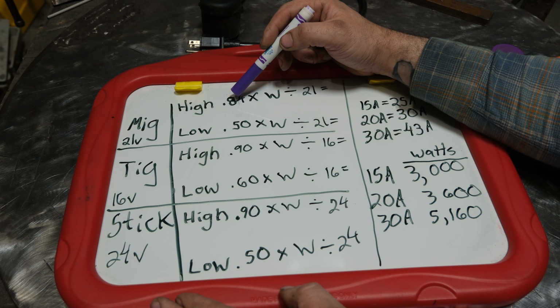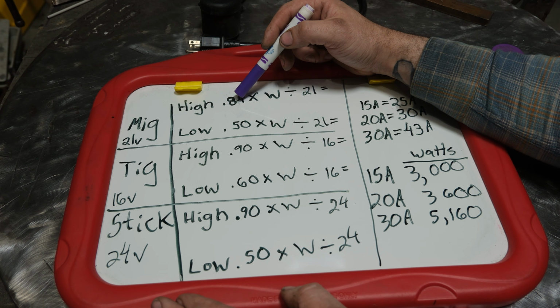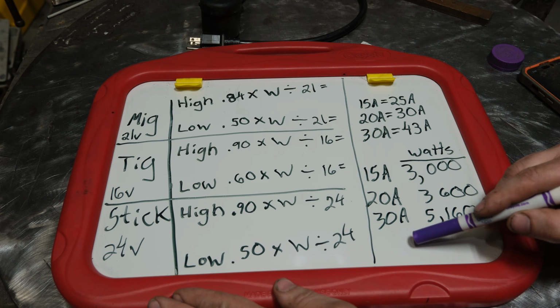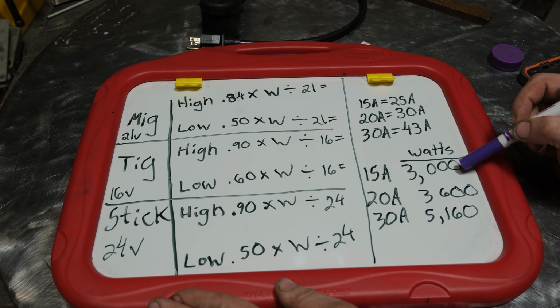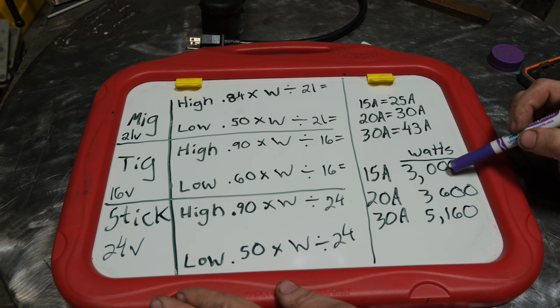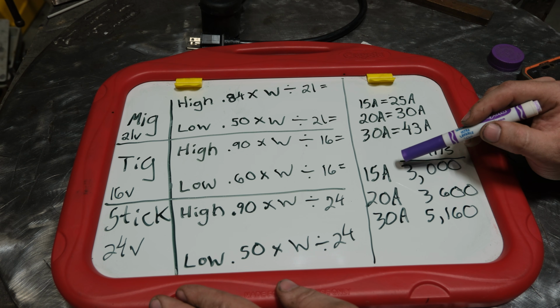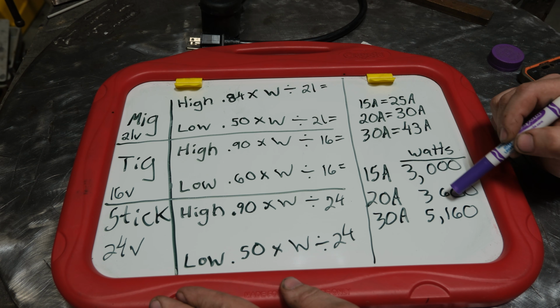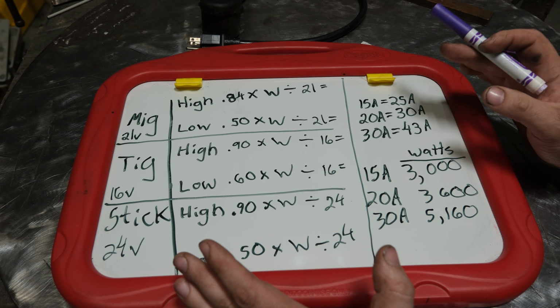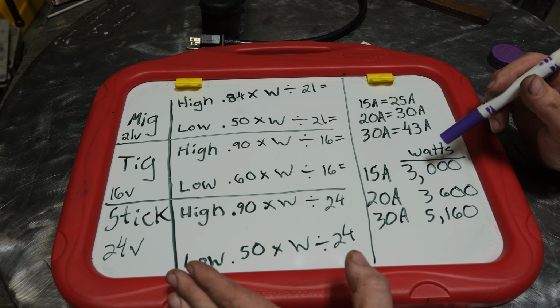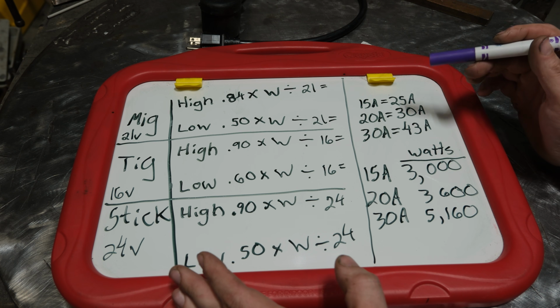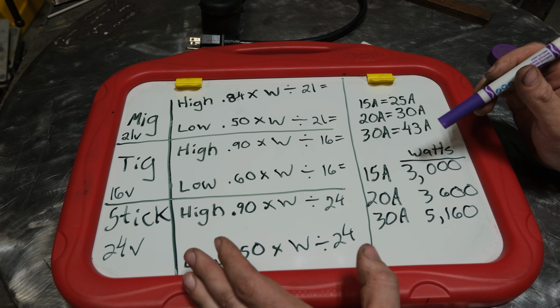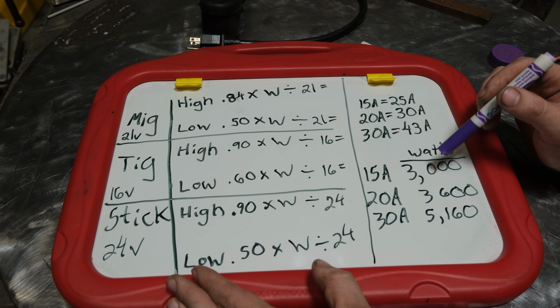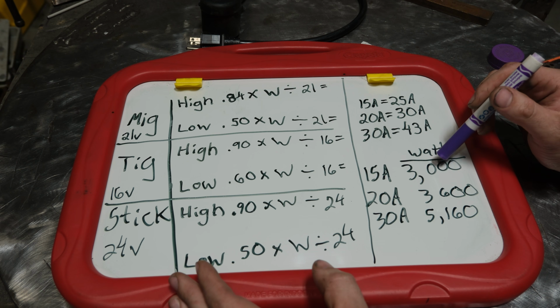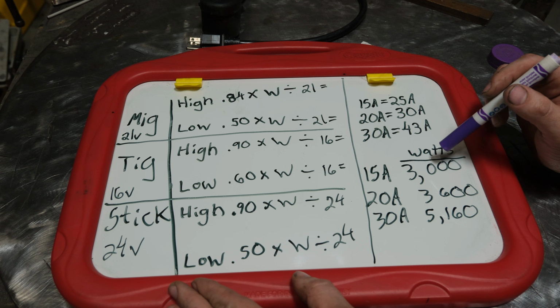So 0.84, and the reason this matters is you take whatever breaker rating you have, and these are the actual wattage that you can probably get from that breaker. Yes, this is overloading that breaker. That is what all 120 volt welders do. They overload breakers. This is nothing new, and people have argued with me over that, but it's the truth, and I'll prove it by the end of this video with an actual test.